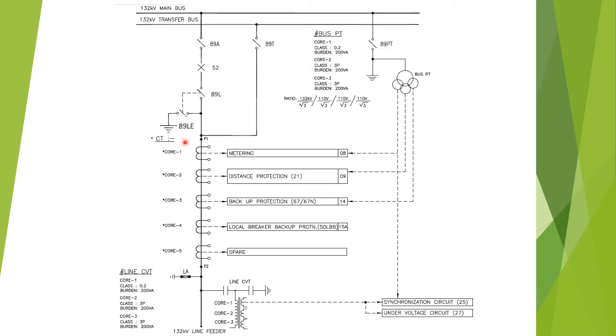This is the 89LE — the line earthing switch. The purpose of 89LE is that after taking proper shutdown from both ends of the substation, 89LE shall be closed so that the trapped charge in the feeder is discharged properly. After that, proper maintenance work on the line can be carried out.